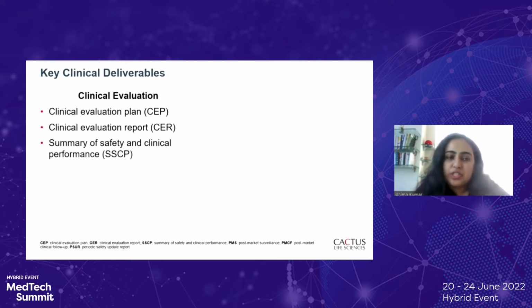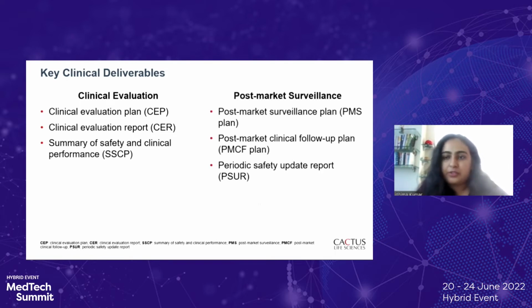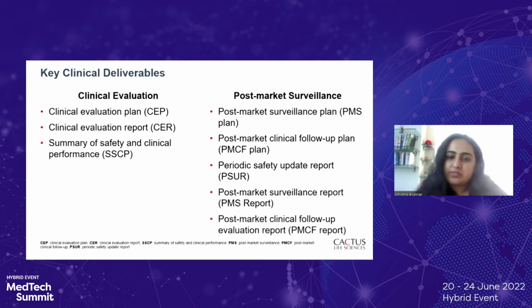On the clinical evaluation side, we have the clinical evaluation plan, the clinical evaluation report, and the summary of safety and clinical performance. On the post-market surveillance side, we have all of these deliverables: the post-market surveillance plan, the post-market clinical follow-up plan, periodic safety update report, post-market surveillance report, and the post-market clinical follow-up evaluation report.